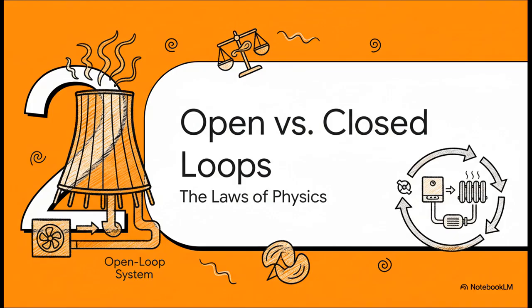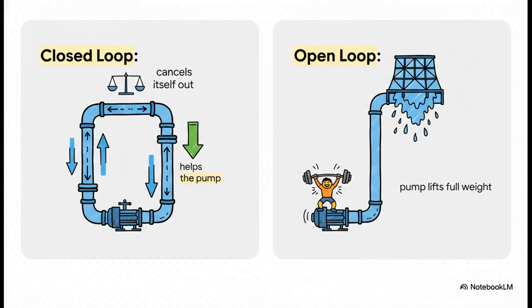It all comes down to the difference between an open-loop system, which is what a cooling tower is, and a closed-loop system, like you'd find in a building's heating. See, in a closed loop, the system is balanced. The water that gets pumped up eventually comes back down, and the weight of that water coming down actually helps the pump push the next bit of water up. It kind of cancels itself out. But in an open cooling tower, that water gets discharged at the top. There's no return trip to help out. That means the pump has to physically lift the entire weight of that water all by itself. It is a much, much tougher job.